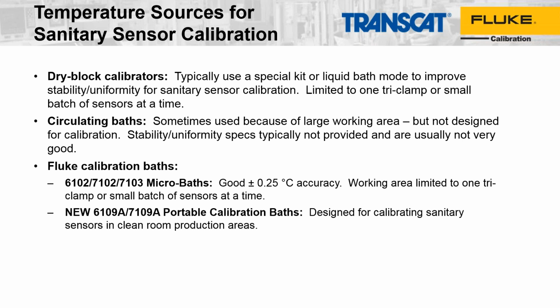Sometimes we'll even see folks taking a calibration bath that's designed to stay in a cal lab and rolling it around a factory, because they really appreciate the larger tank size and the ability to put sensors of all different sizes and shapes down into the fluid to get a better calibration. But these larger baths are again designed typically for the cal lab, and they may take a long time to change in temperature. They have very, very good stability and uniformity specs, but aren't really ideal for use out in a factory setting or out in the field.